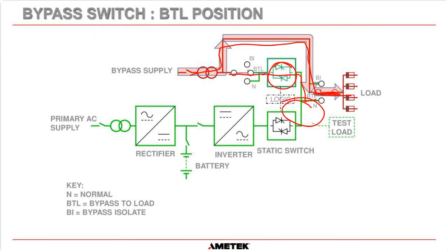That allows us to do testing. If we powered the system down and replaced some parts, when we power it back up again, we can go to the bypass to load position and test the synchronization between the inverter and the bypass, and put a load bank on the output if we wanted to, and test the inverter.